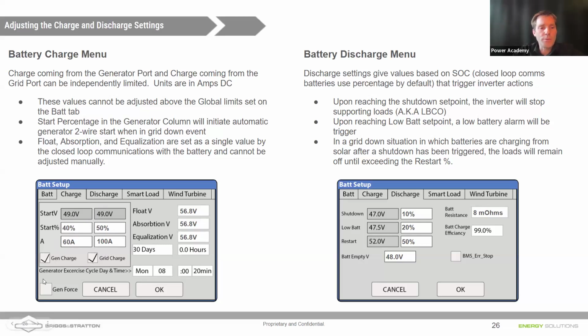Now, Daniel, there's a Gen Force box down here. There's also a generator exercise cycle. What have we done here with the hours of the generator exercise cycle? Well, keep in mind a lot of generators, including our Briggs & Stratton Power Protect line of generators, have the exercise functionality built into them. So what you're seeing here is the Sol-Ark can exercise the generator for you, but by setting all those values to 0 minutes, 0 hours, you'll rely on the generator to do its own exercise functionality. You could theoretically operate it here. For the Gen Force, you click that and then hit OK. Remember, in Sol-Ark, hitting OK is kind of the save button. That would force the generator to start up so you can test it as well.